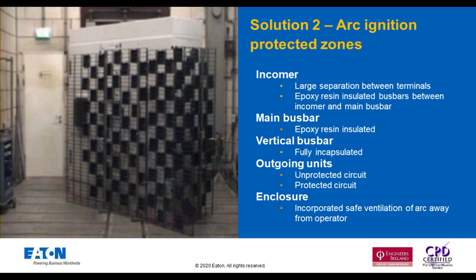This is where you can ensure that, within that compartment, the likelihood of an arc happening is reduced by various methods you can apply, like insulating the internals of the copperwork. And then the enclosure itself, you can incorporate a ventilation of the arc away from the operator. So under the IEC Technical Report 61641, which is a guide for testing under conditions of arcing due to internal faults, it identifies design features which will reduce the risk of arc flash hazards.